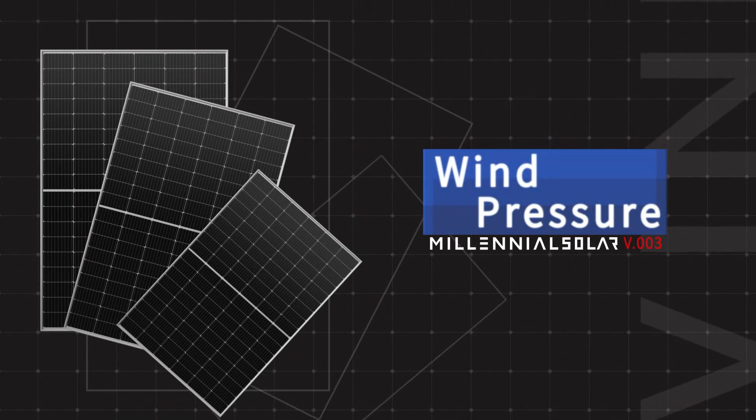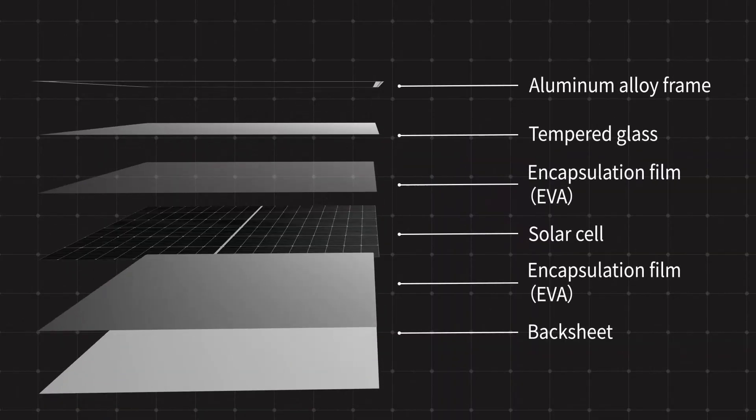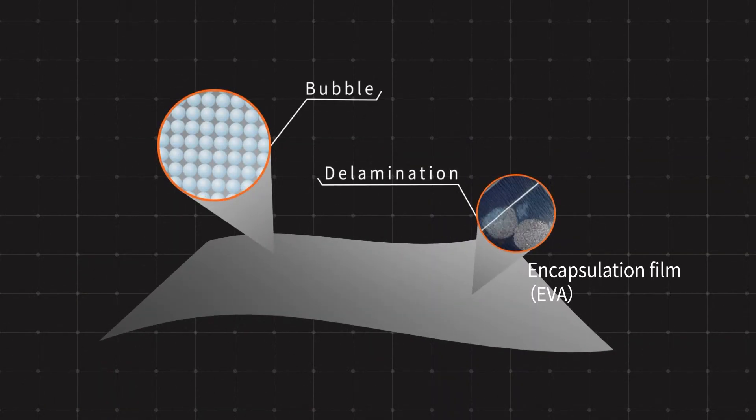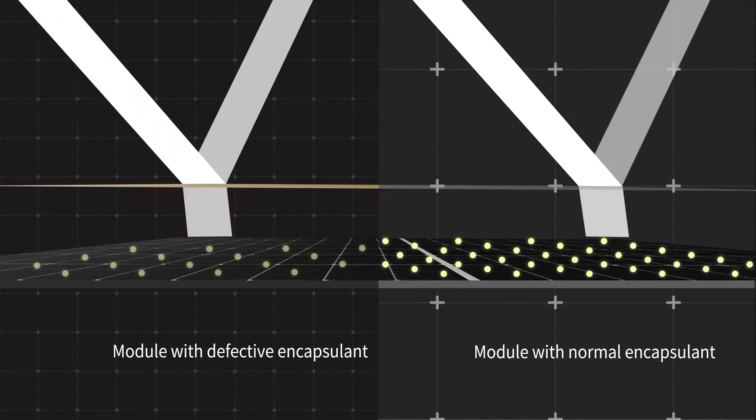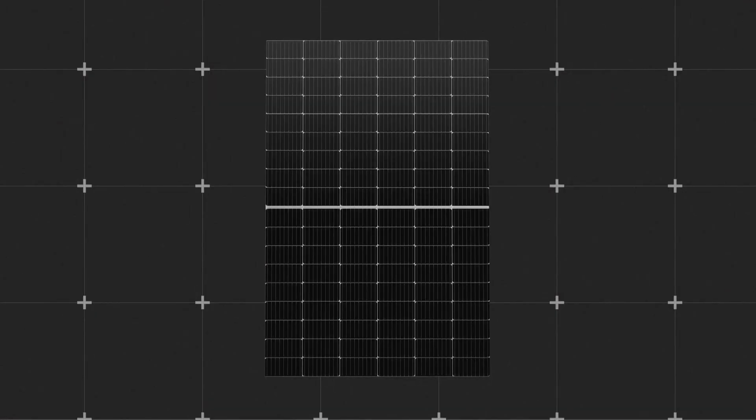These cyclic dynamic stresses are key culprits of material aging. Encapsulant films may fatigue, causing bubbles or delamination, which leads to water ingress, yellowing, and reduced heat dissipation and light transmittance, directly resulting in power degradation.